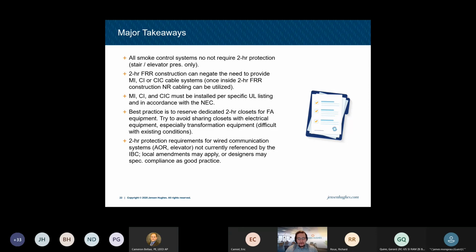The risk isn't as high with just switchboards and non-combustible conductors, but once you get into transformers, you're really not addressing the intent of the code, which is to basically have a system that can be survivable from any fire in the building, with the exception of obviously a fire resulting in the fire alarm system itself. So it's one of those things that was historically done. It continues to be done. But if you're an engineer and you can get it ahead of time, it's not a lot of space, and it's really going to result in the most survivable system for the building.